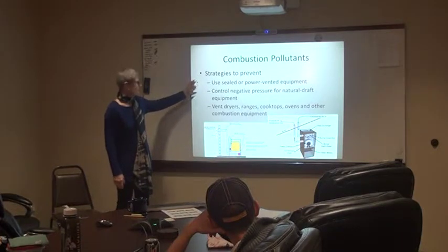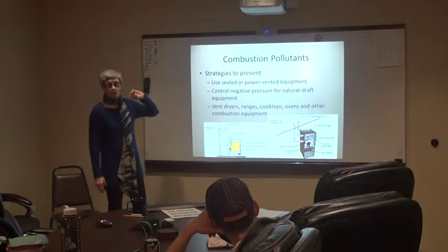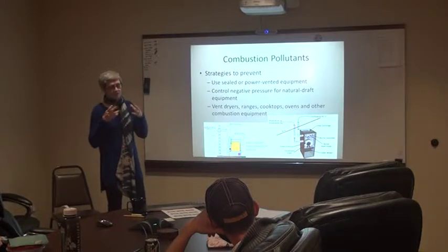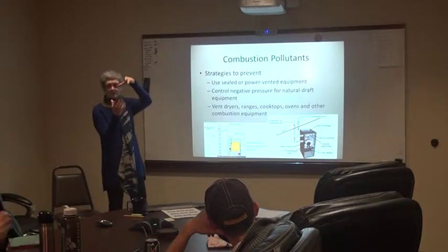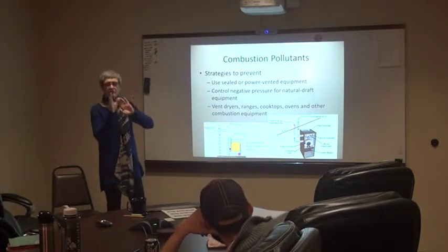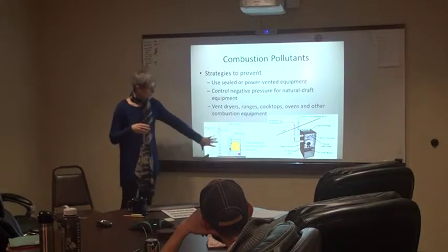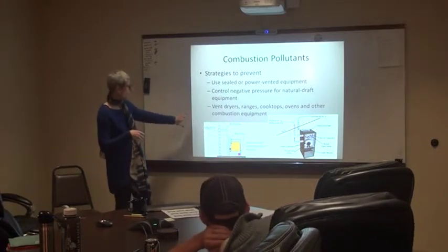My son and I just moved to a house in April that has an atmospherically vented water heater that was orphaned. It's functioning okay now. It's got a pretty good draw, but I don't want to live with that. And not only was it orphaned, it was put into a vent size that now is illegal. So if something happened to turn that around, we could have some carbon monoxide issues because the burning process would not have enough oxygen to burn correctly.